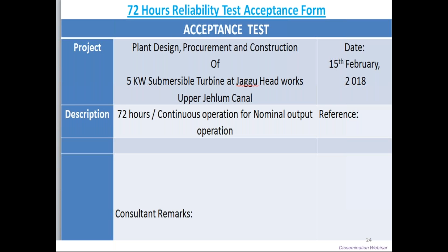It is to be filled for 72 hours. From 0 hour to 72 hours, it will be recorded and signed by the EPC contractor, manager construction, and client or owner of the turbine. So here we see how phase-to-phase voltage, phase-to-phase current, power factor, total power, frequency, kVAR, RPM, stator winding temperature, generator temperature, turbine bearing temperature, and grid voltage are all recorded for 72 hours and signed by every stakeholder.